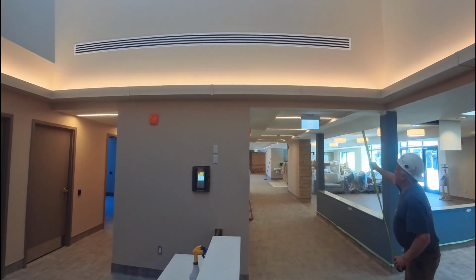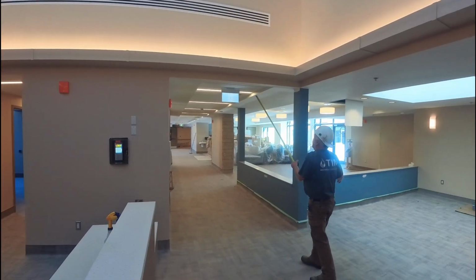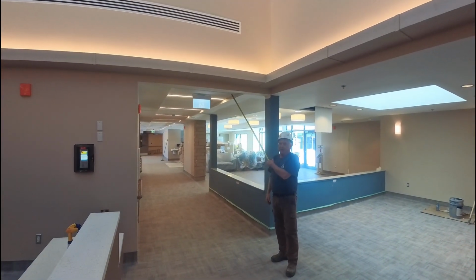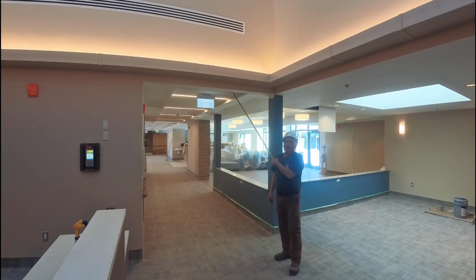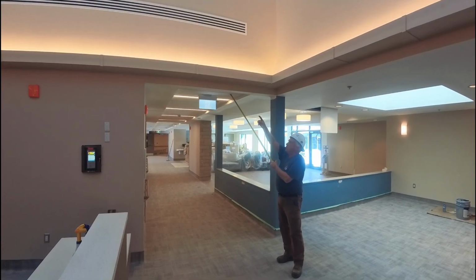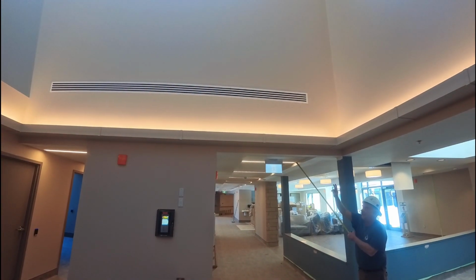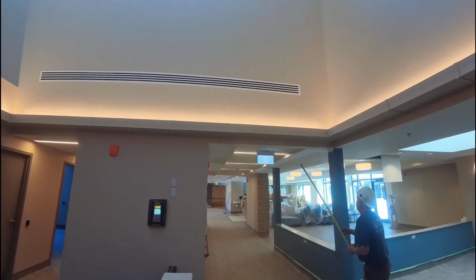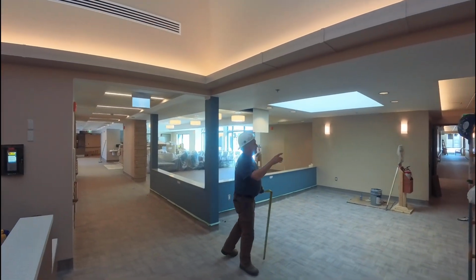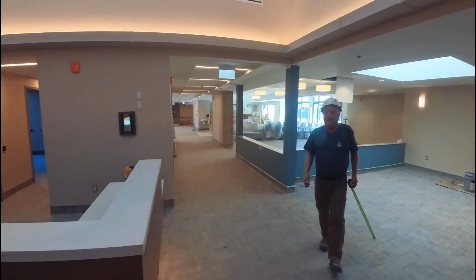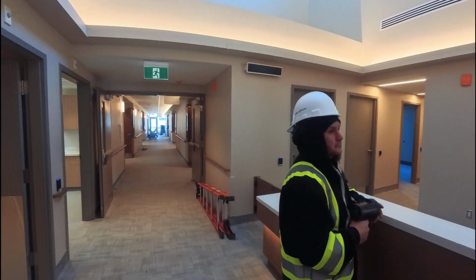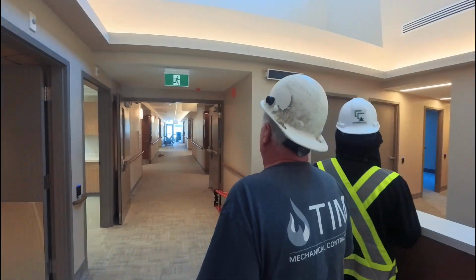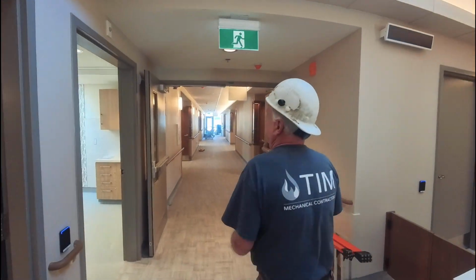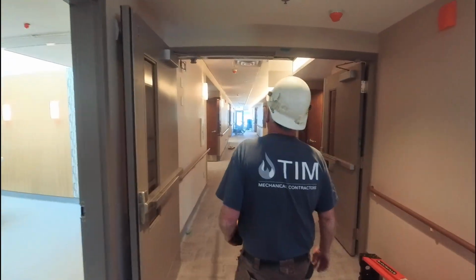It has one diffuser with one balancing damper up there above the T-bar right there, which picks up this one long linear. Because most of the air is closed, I want to say 3/4 to 7/8 closed, because it's just a little bit of air for that big diffuser. It's 3 10-inch rounds feeding that, I believe. You want the bulk of your air to come out because we're feeding all the individual wings and fan coil units that are placed around the different rooms.